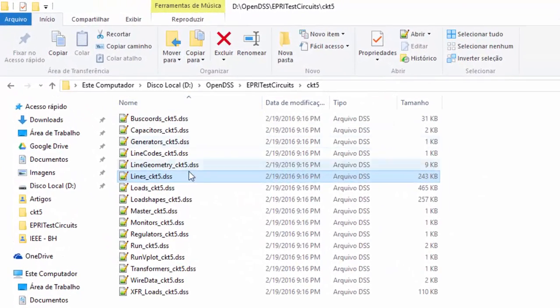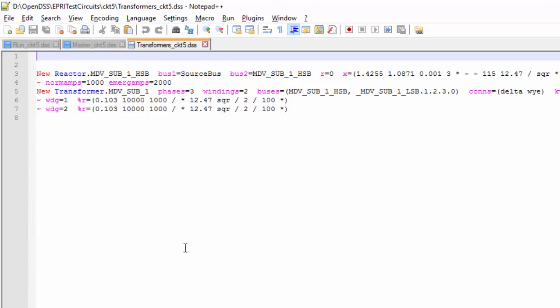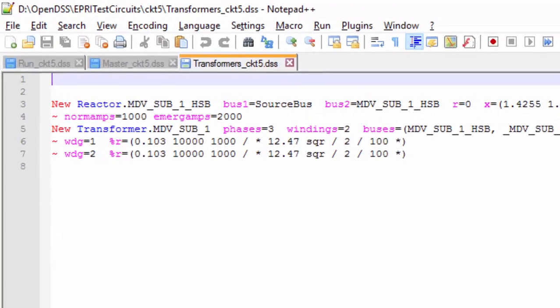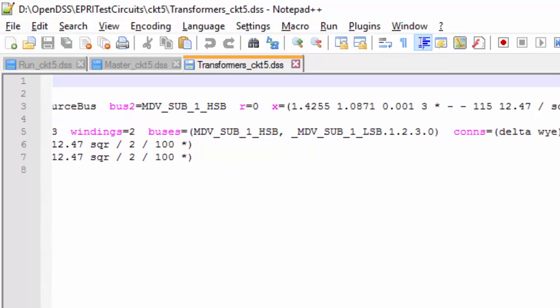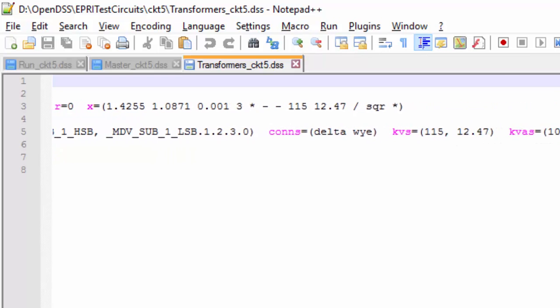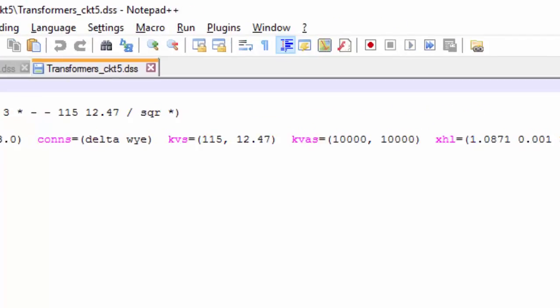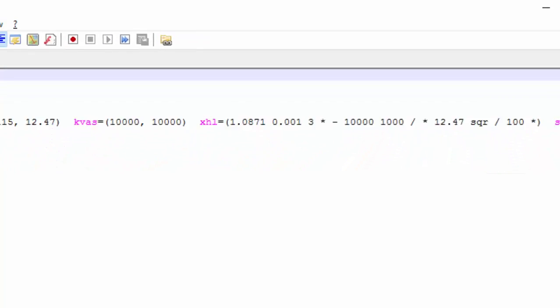Let's see what we have inside the transformer circuit5 DSS file. There is a reactor which is modeling a series impedance of the circuit element, as you can notice the source bus here. Then, there is the substation transformer. Pay attention that the sub property is set to yes, which means that this transformer will be recognized by OpenDSS as a substation and will be shown in the circuit plot with a mark and its name.